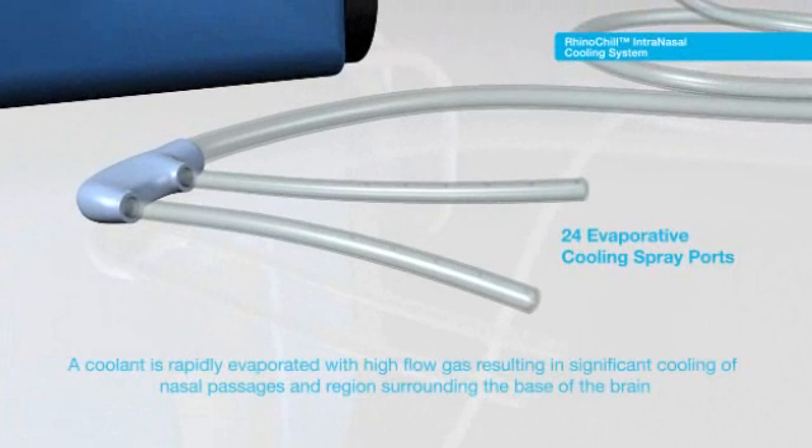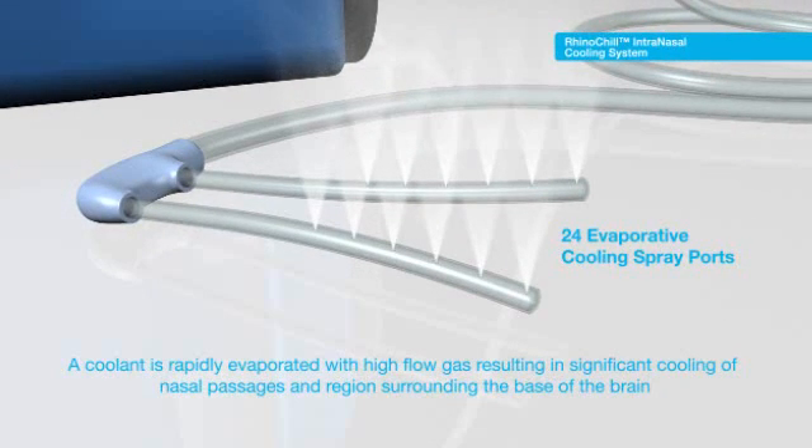With 24 evaporative spray ports, the RhinoChill System Coolant is rapidly evaporated under high-flow gas, resulting in significant cooling of the nasal passages and region surrounding the base of the brain and local blood supply.